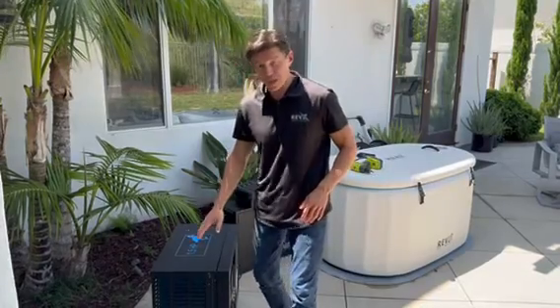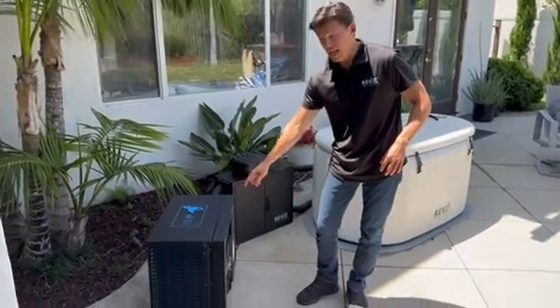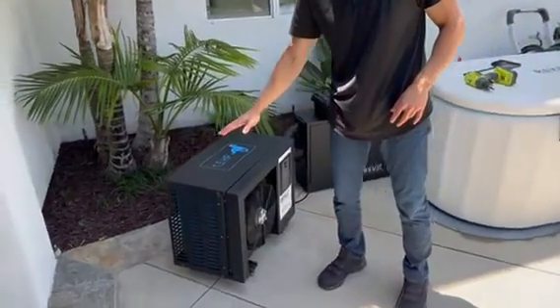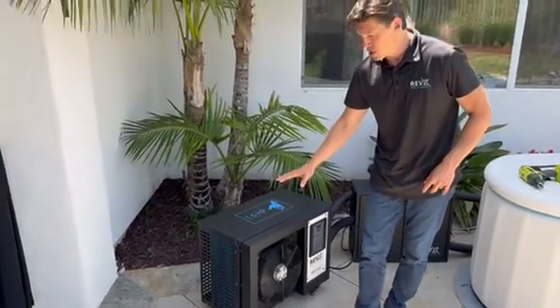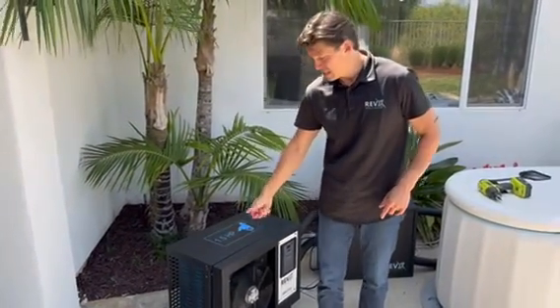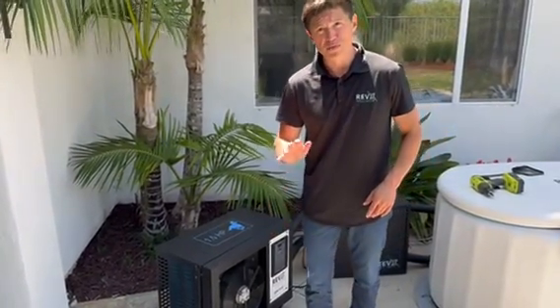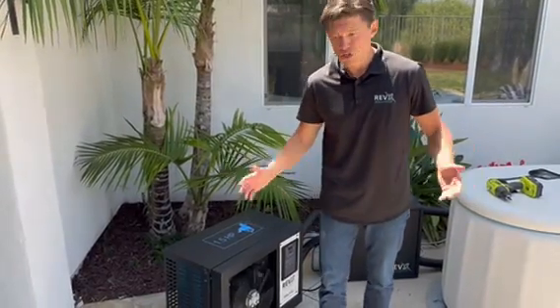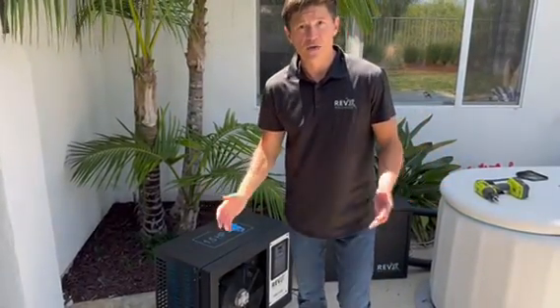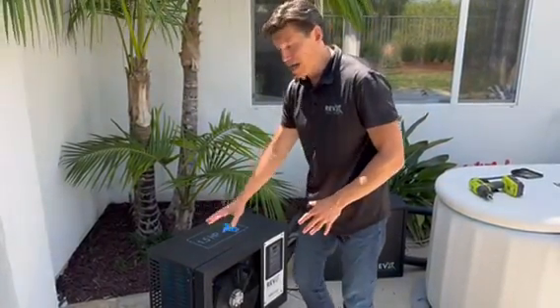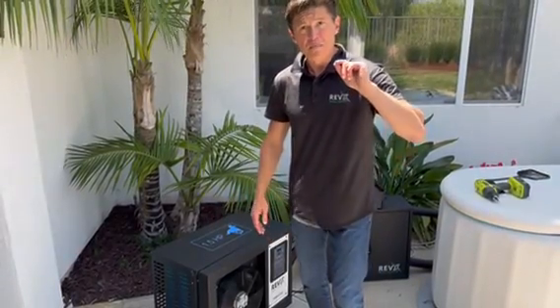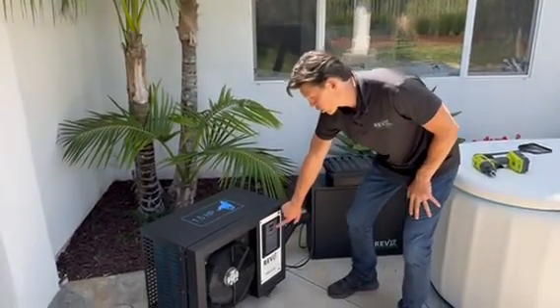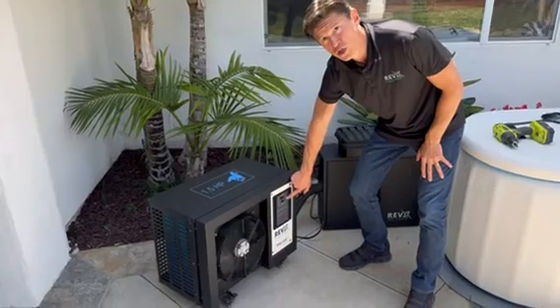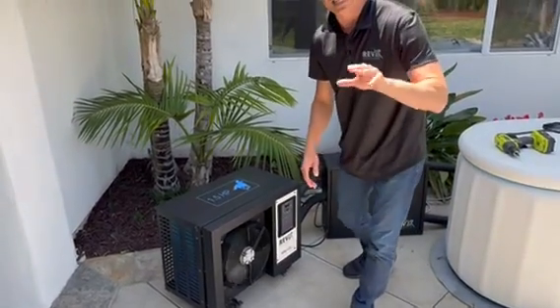So right now, what you hear is a spinning fan and the compressor's on. This is great functionality. This is great audible noise. The dB level right now is roughly between 70 to 75. It's just like a loud fan inside your house. This is normal. So if you hear anything else other than that, immediately what you want to do is turn off the chiller. Okay? Turn off the chiller immediately and contact us.